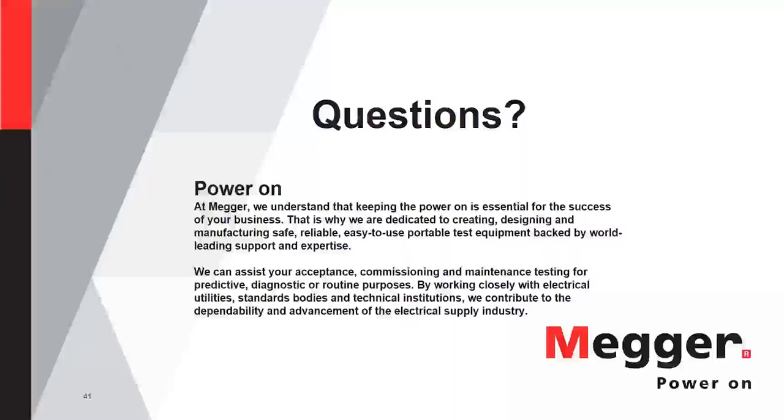And again, if you're talking about ripple voltage and ripple current, the most predominant source of that would be the charger. Typically, like I said, in substation applications, the charger would be your primary culprit. If you saw a very high ripple on big flooded batteries, typically it's going to be a bad rectifier in the charger. But like I said, in telecom applications, you may see things coming from the load at higher frequencies causing that. And that's where a spectrum analyzer can come in handy.